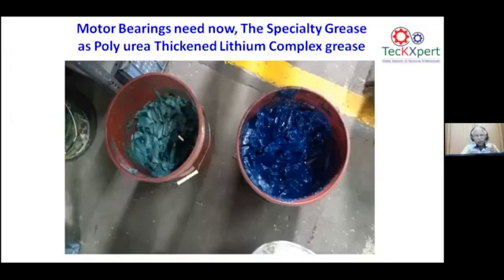I have come across an industry where a manual winding machine motor was running at 112 degrees on an ordinary MP3 grease put on the motor bearings. This was removed the next day and changed with this polyurea thickened specialty grease. From 112 degrees, it just came down to 80 degrees within 4 to 6 hours of operation, and the motor became very steady. The power consumption is also reduced, and at the same time the motor health is improved.